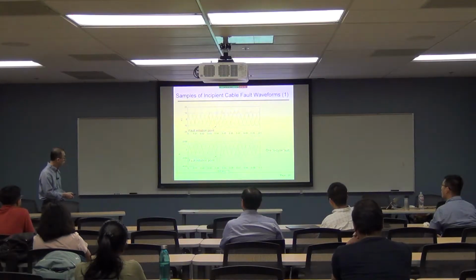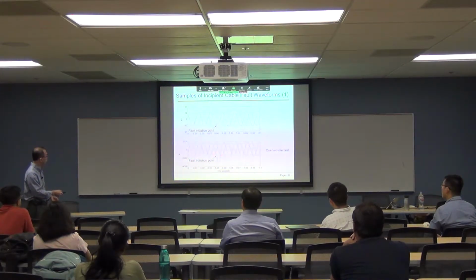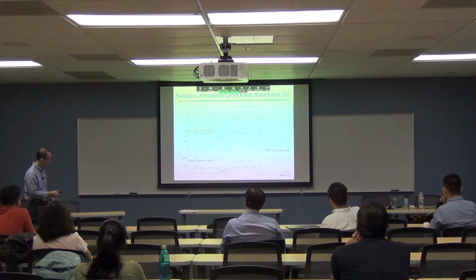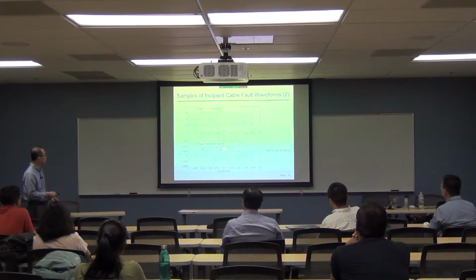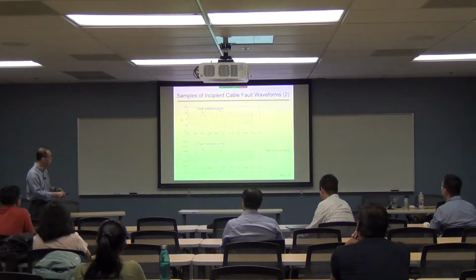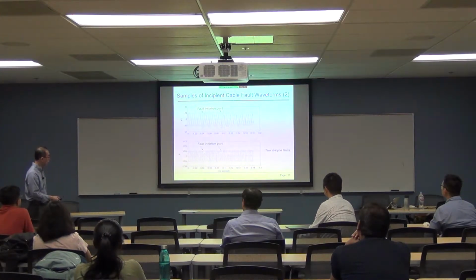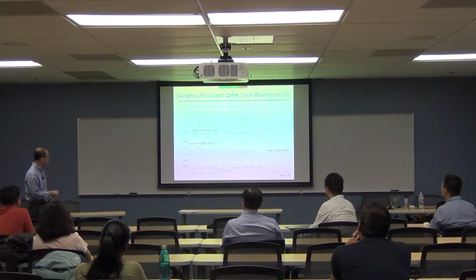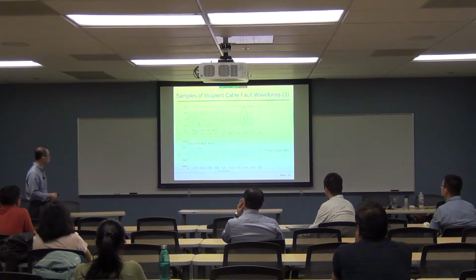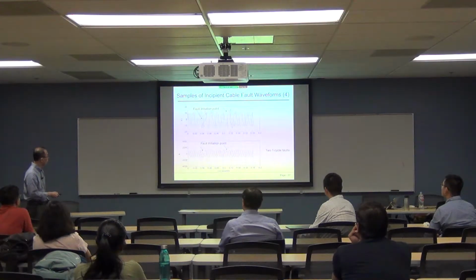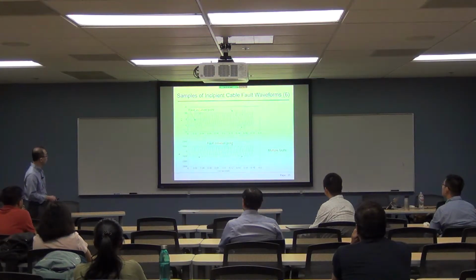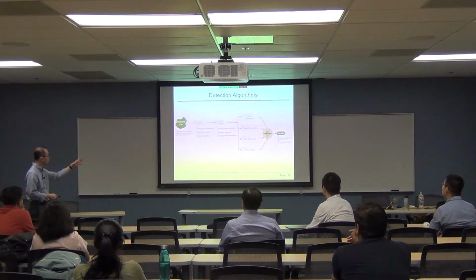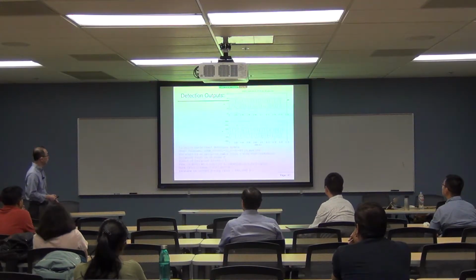So let me show you some of this quickly. You can see that this is the fault point. Sometimes it is only a quarter of a cycle, okay? Sometimes there is half a cycle happening here, but nothing happened before. So this represents a good opportunity for us to detect it before it actually happens. Some are actually 1 cycle, but it doesn't cause a full-blown fault. Some are 2 cycles. Some are 1.5 cycles. Some are multiple, coming in like here, here. So this is a simple algorithm, basically just signal processing, okay?